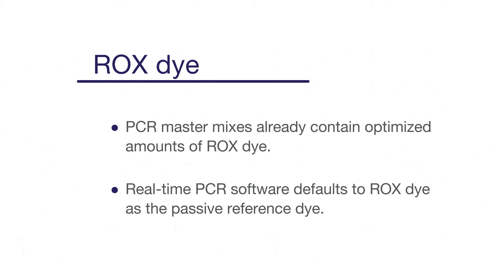Otherwise, the software will attempt to normalize to a dye that's not there — not a good thing. Alternatively, if you need to use a different passive reference for multiplexing purposes, like Applied Biosystems' Mustang Purple dye, you can select another option within the software.